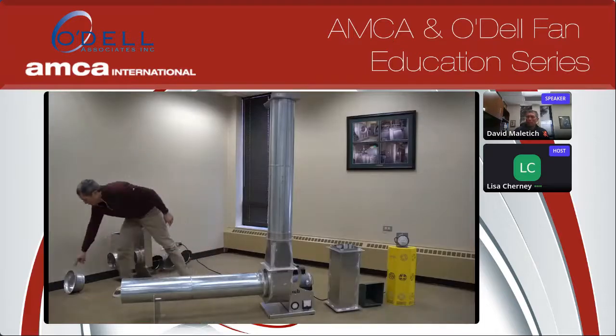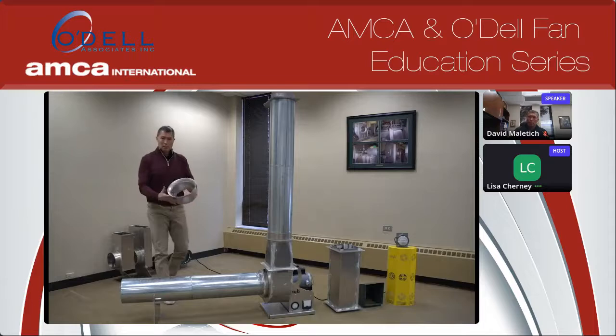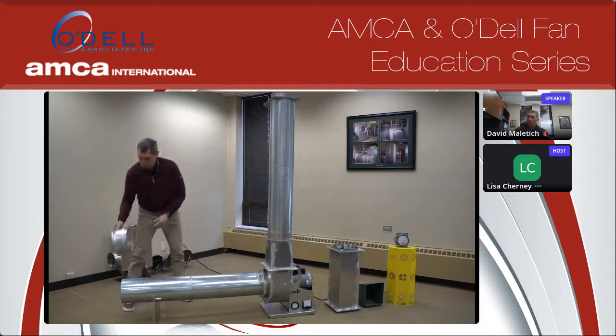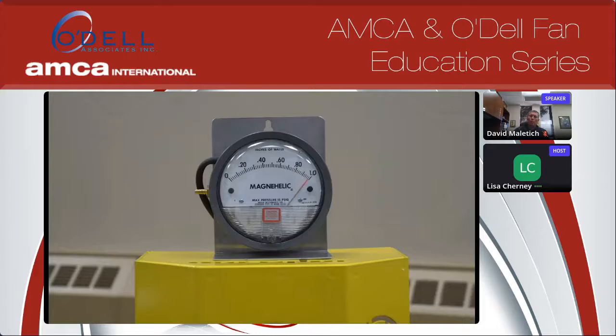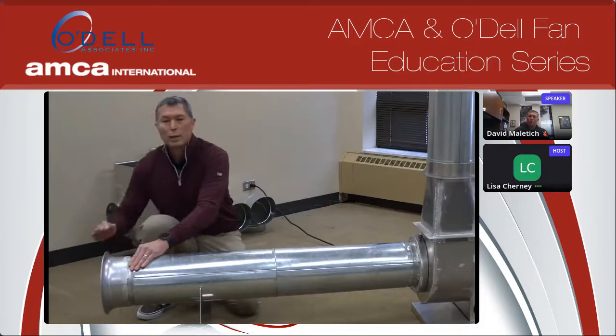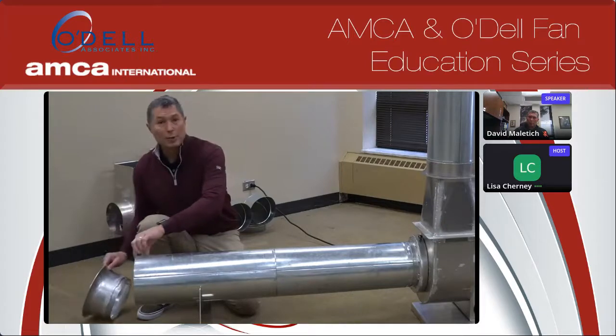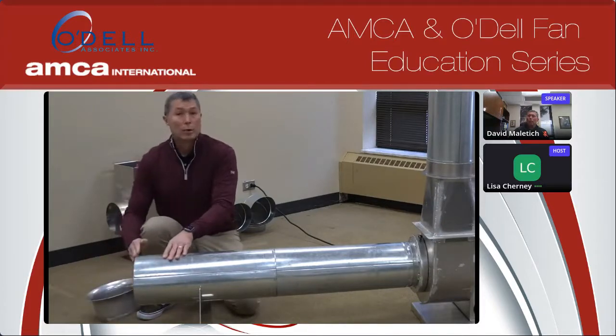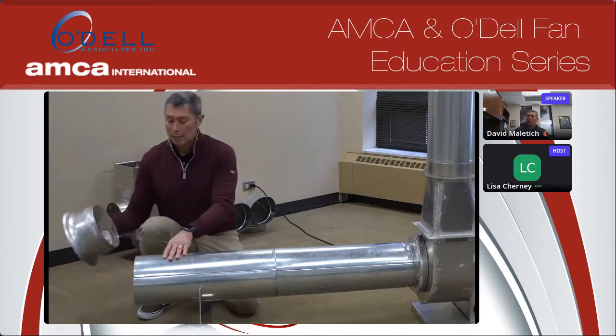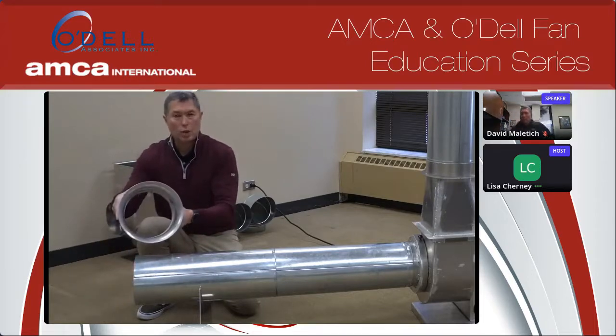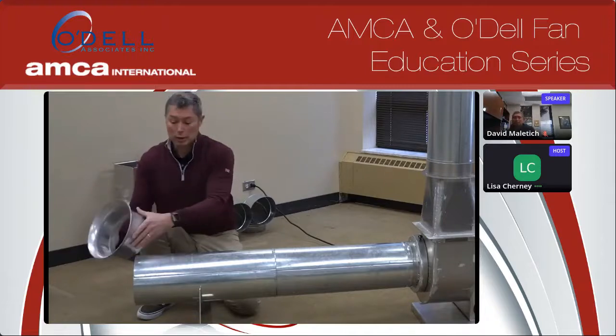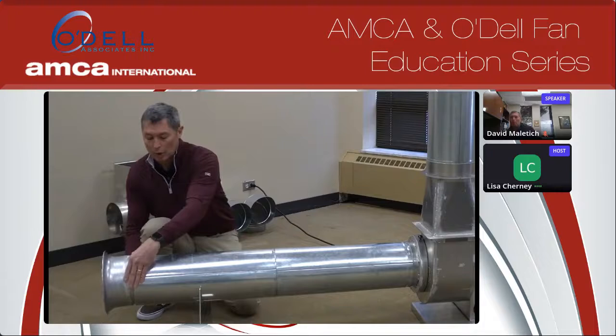Now, if we add this venturi to the inlet, just a plain venturi, see what happens. You'll notice that almost all the losses associated with the straight run of ductwork are gone; there's virtually no loss. And what you soon realize is that those losses are associated with the entry loss over this sharp-edged orifice. And that entry loss is pretty significant, almost 1/10 of an inch. By putting this venturi on the inlet, you've eliminated almost all of those entry losses. And we can watch the Magnehelic again.